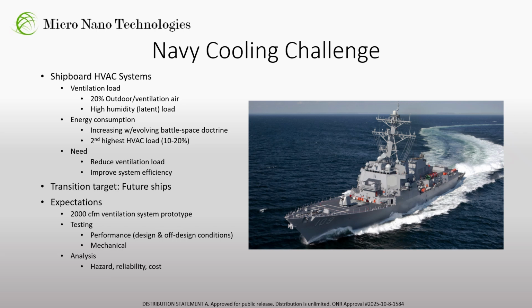In the winter season, shipboard HVAC systems use electric heaters to heat the incoming ventilation air, creating a significant electrical demand. These ventilation systems are used to supply ventilation air to multiple recirculation air systems. In these recirculation systems, the conditioned ventilation air provided by the ventilation system is combined with the recirculation return air before it is cooled and distributed within the ship. Evolving battlespace doctrine, emphasizing operations in both the littoral and Arctic, as well as changing climate conditions, are further increasing these loads. As such, there is a significant need to reduce the ventilation latent load and improve efficiency, while reducing the size, weight, and electrical power consumption of shipboard HVAC systems.